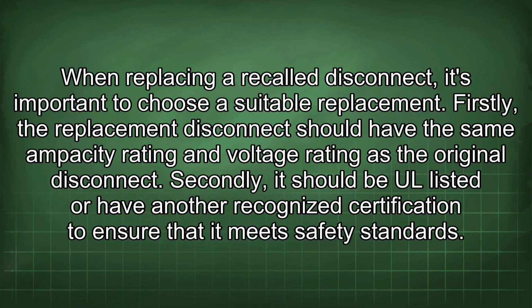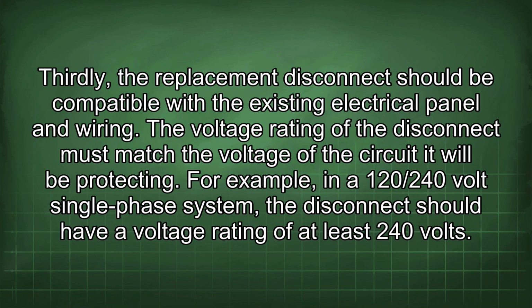When replacing a recalled disconnect, it's important to choose a suitable replacement. Firstly, the replacement disconnect should have the same ampacity rating and voltage rating as the original disconnect. Secondly, it should be UL listed or have another recognized certification to ensure that it meets safety standards. Thirdly, the replacement disconnect should be compatible with the existing electrical panel and wiring.